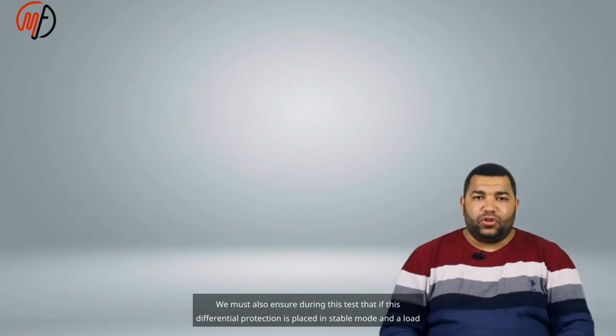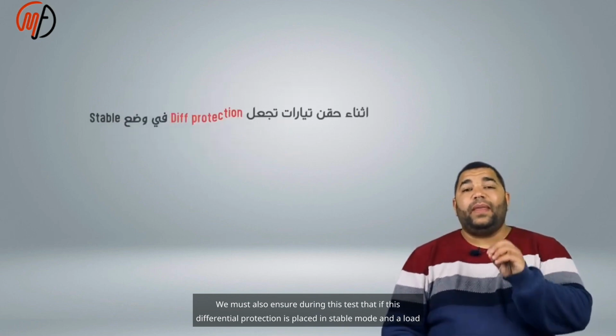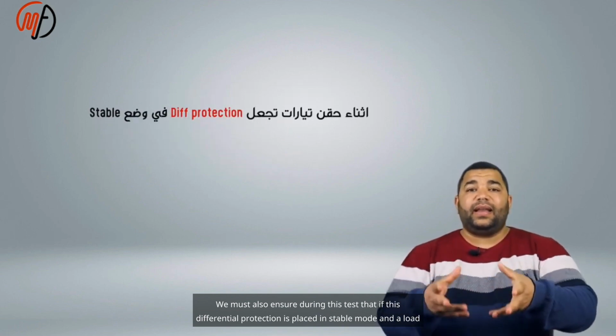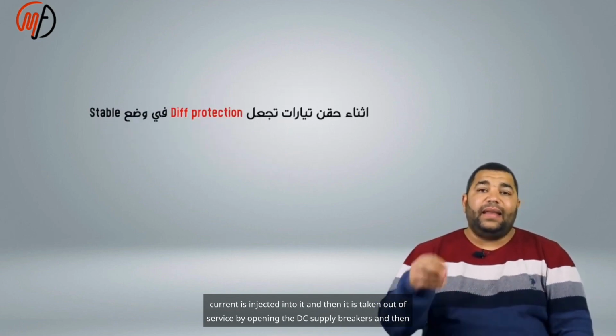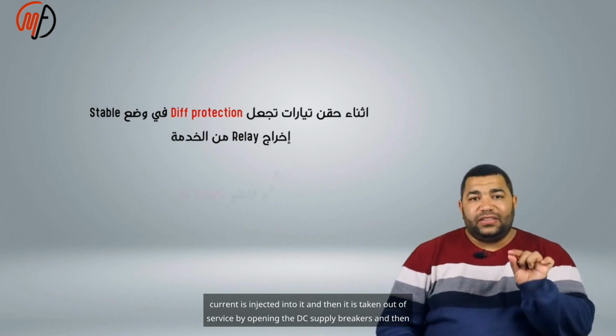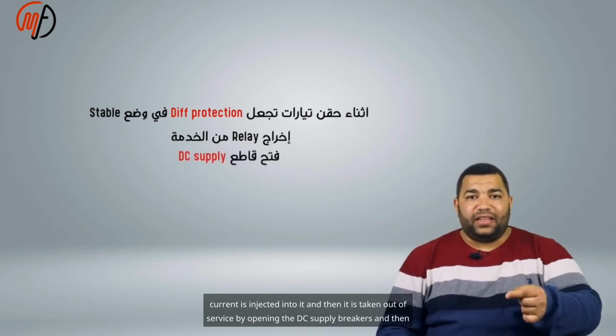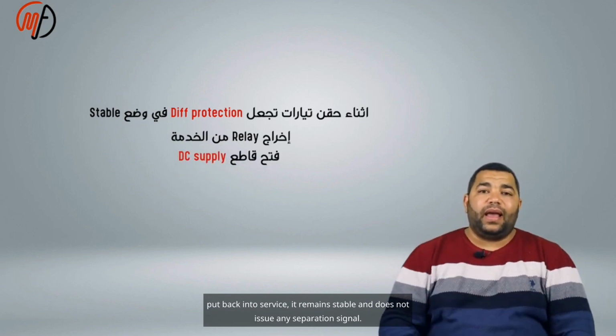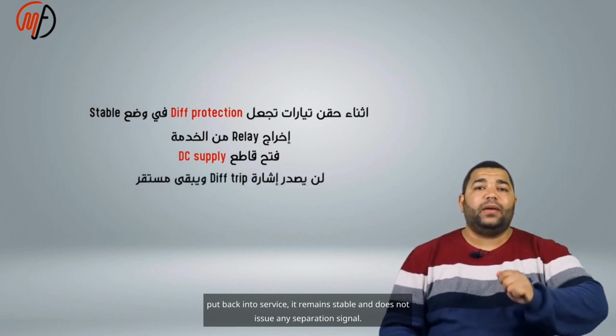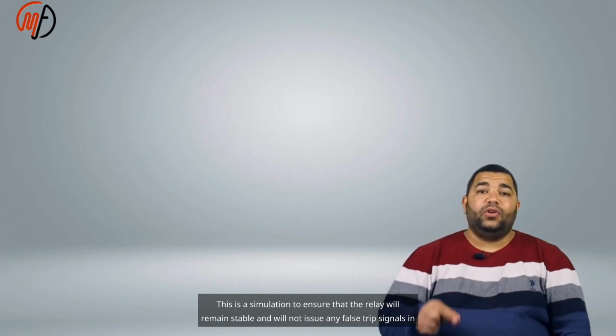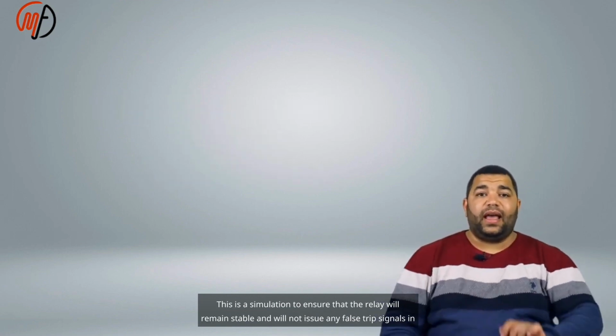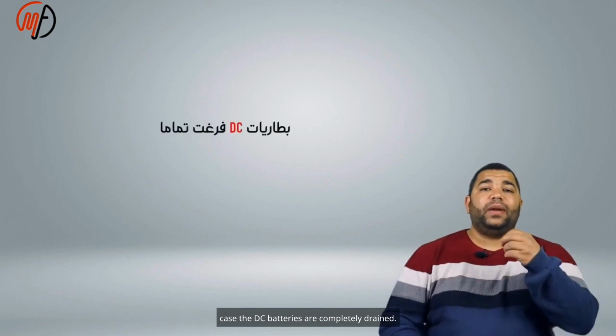We must also ensure during this test that if this differential protection is placed in stable mode and a load current is injected into it, and then it is taken out of service by opening the DC supply breakers and then put back into service, it remains stable and does not issue any separation signal. This is a simulation to ensure that the relay will remain stable and will not issue any false trip signals in case the DC batteries are completely drained.